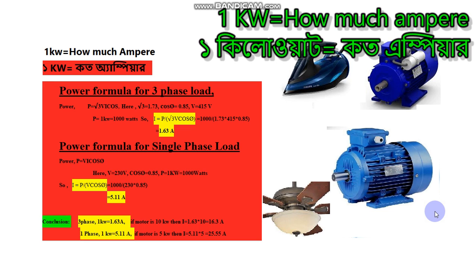Rearranging for current: I = P ÷ (√3 × V × cosθ). Substituting values: I = 1000 ÷ (1.73 × 415 × 0.85). Solving this equation, we get 1.63 amperes as the ampere rating of a 1-kilowatt three-phase load.